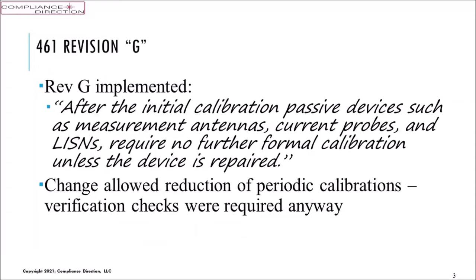Also, Revision G came out in 2015 and implemented a calibration change. Reading the statement: after the initial calibration, passive devices such as measurement antennas, current probes, and LISNs require no further formal calibration unless the device is repaired. Well, that came about to help reduce some of the costs of keeping instrumentation in calibration when there's very little chance that it was a problem. Items that are used once in a great while get put away and taken care of, and we pull them out and make sure that nothing has deteriorated through a physical inspection and things like that, and check these verifications to see that they're still working within their calibration levels. In other words, the correction and conversion factors are still applicable.